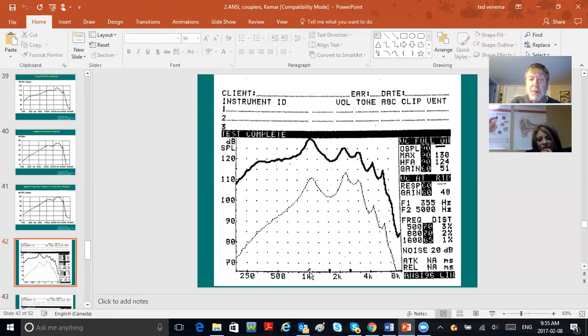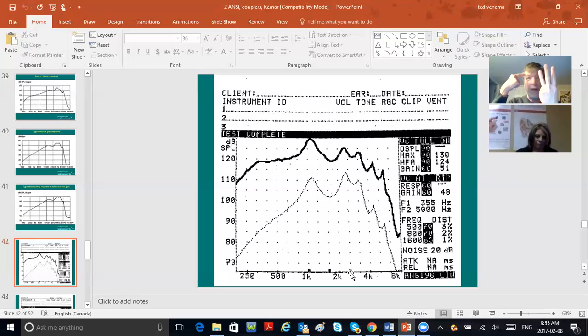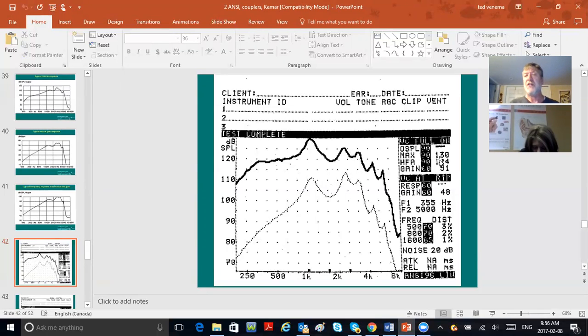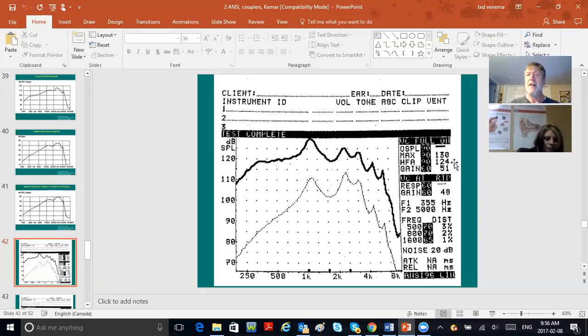The third item shown is the HFA—high frequency average—the output at 1000 Hz, 1600 Hz, and 2500 Hz. Memorize those three frequencies: 1k, 1.6k, and 2.5k. Those are the high frequency averages always done in ANSI testing. Add those three output values together, divide by three, and you get your high frequency average—in this example, 124 dB SPL.